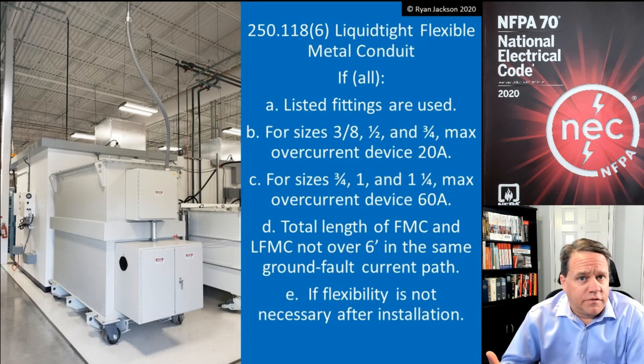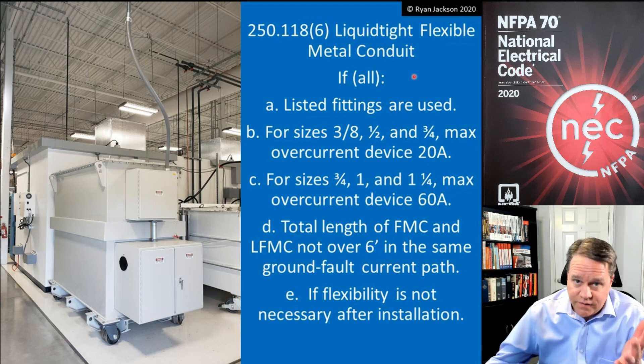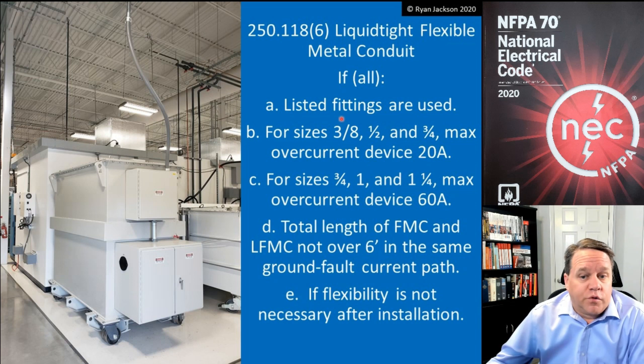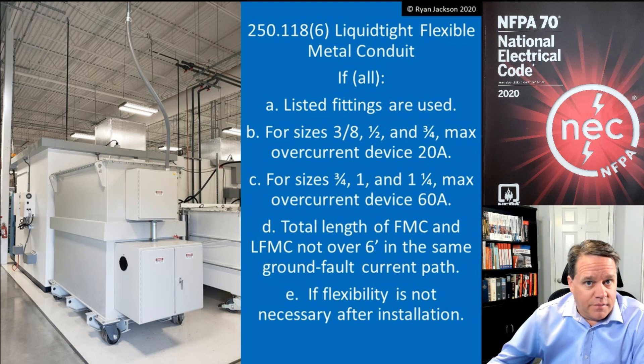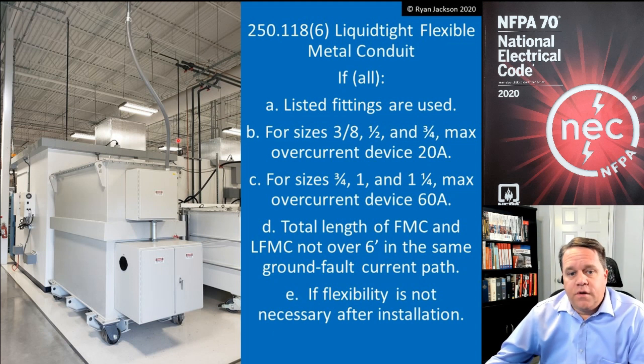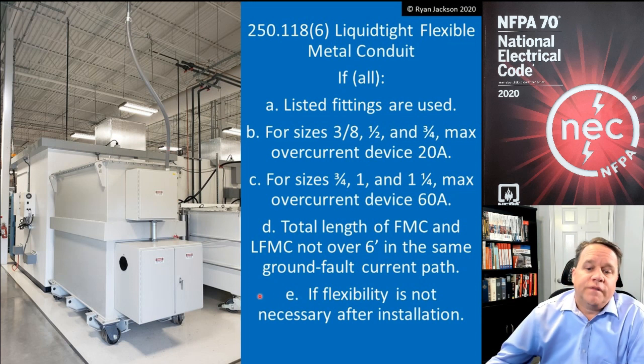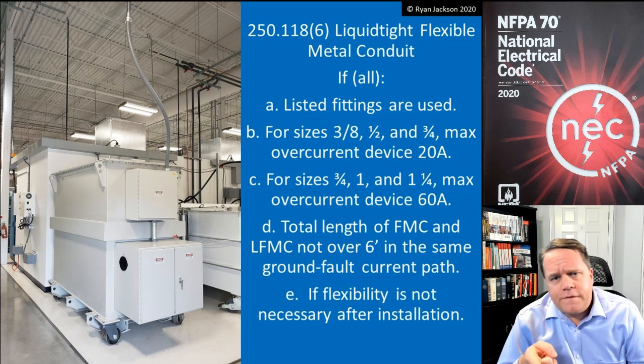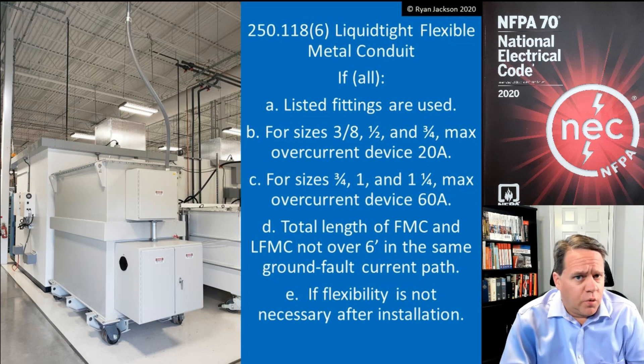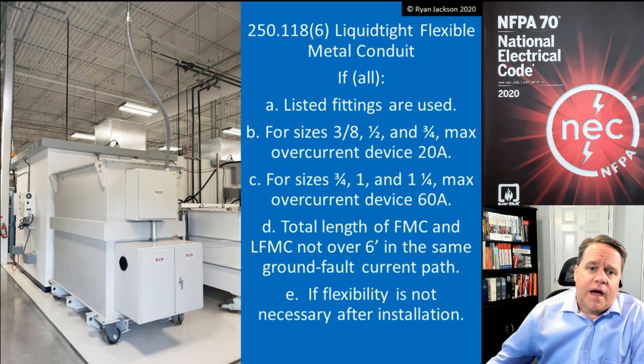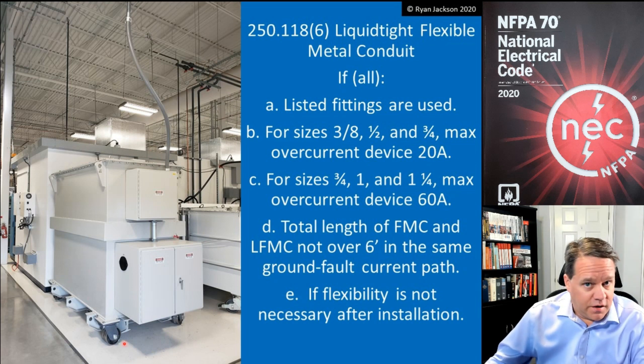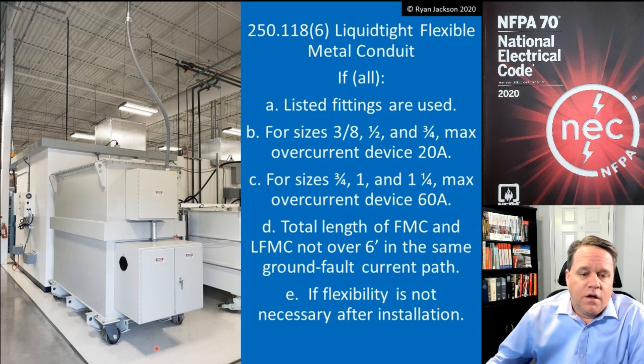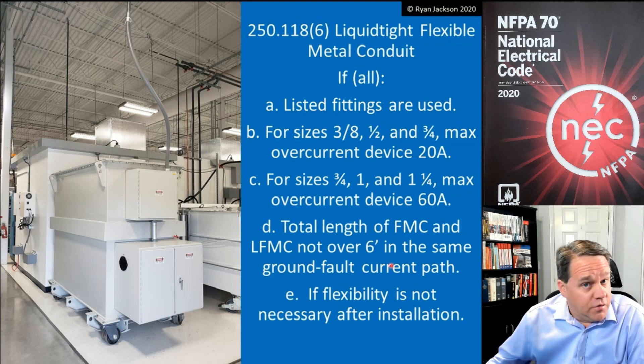We have similar allowances for liquidtight flexible metal conduit. You must use listed fittings. For ⅜, ½, and ¾-inch sizes the maximum overcurrent device is 20 amps; for larger sizes up to 1¼ inch you can go up to a 60-amp circuit breaker, as long as total length does not exceed six feet in the same ground fault return path, and flexibility is not needed after installation. Looking at this picture, if this raceway is one inch or 1¼ inch I could have up to a 60-amp breaker and not need a green wire — but notice it has wheels, so flexibility is needed after installation.